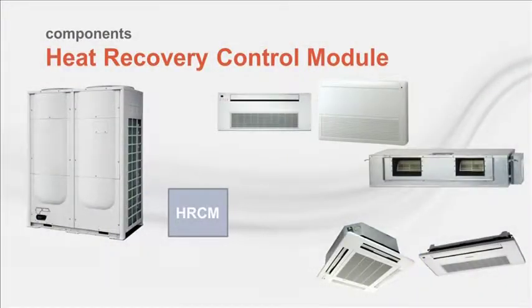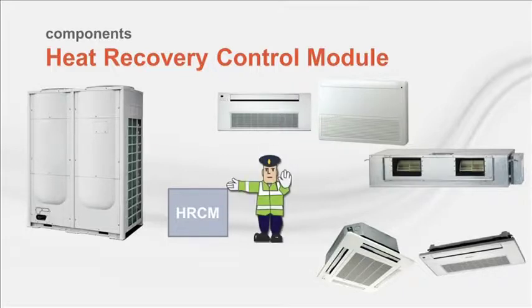On the other hand, heat recovery systems have the ability to provide simultaneous heating and cooling because both high-pressure gas and liquid refrigerant are available to the indoor units. The heat recovery control module, shown here as a gray box, enables the system to provide both heating and cooling simultaneously. For heat recovery systems, the control module acts like traffic police in that it's able to direct either hot gas or liquid refrigerant to the individual indoor units.